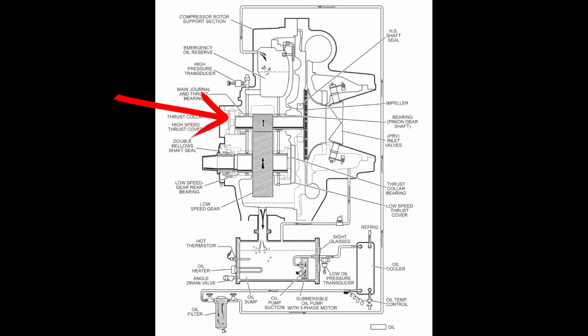Now this is a very small space here, so keep that in mind. Basically the bearing itself is just a set of touchdown pads. I wouldn't say rubber, that's not a good description, they're a set of pad points that when there's extreme axial shift, a surge for example, and this impeller gets driven one way or the other, but specifically to the back, these pads are able to do a slight touchdown and prevent a catastrophic failure from extreme metal slamming into each other at high speeds. Because keep in mind, this shaft here is operating at 20-something thousand RPM most of the time.